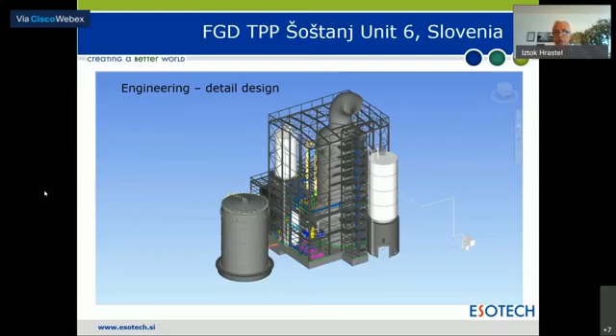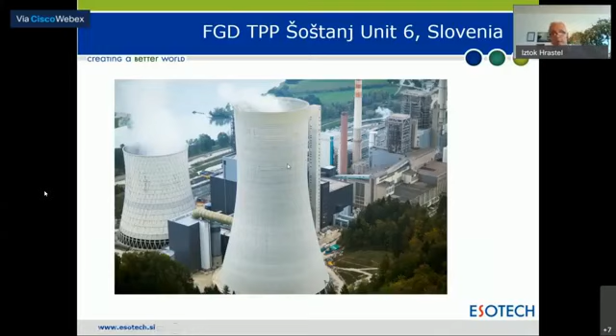After process chemistry calculation and basis design, we continue our design with CFD modeling in order to optimize our solution, in terms of flue gas velocity harmonization over the absorber cross section. You can see flue gas velocities in this cross section, achieving the most efficient SO2 reduction in the FGD plant. There are 4 pictures: this is the inlet, and this is the top of the absorber.